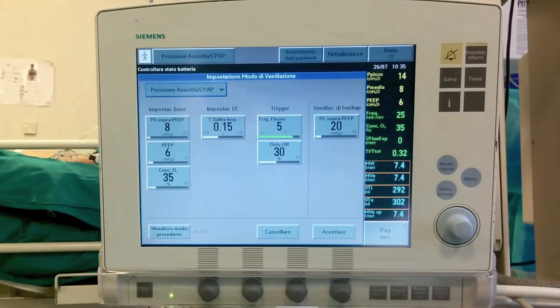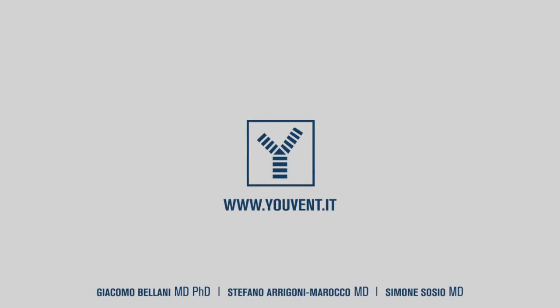In conclusion, the settings we can use to regulate the PSV are PEEP and pressure support above PEEP, flow triggering versus pressure triggering, cycling off criteria, and eventually back up setups in case of apnea.